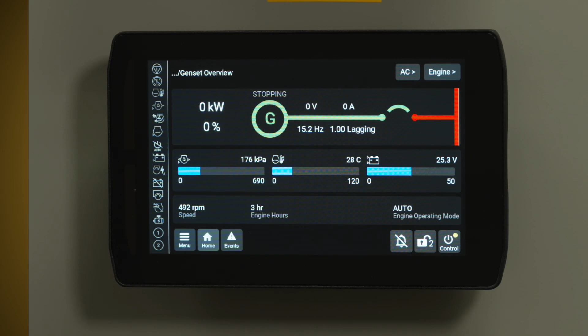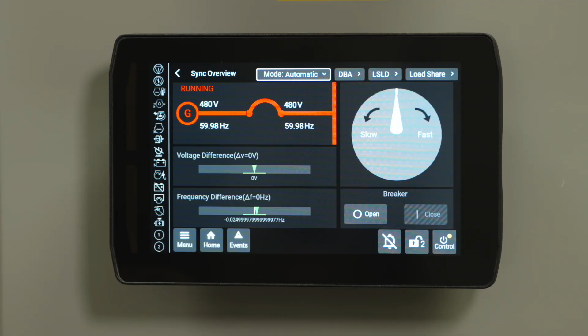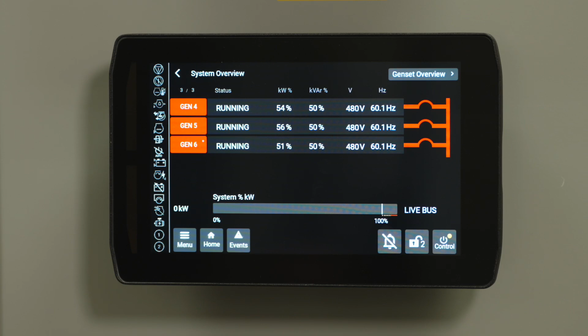As Vic has mentioned, we support enhanced PLC capability. This allows us to leverage Caterpillar logic and patented algorithms into features such as paralleling and load sharing. Just like our previous genset controller, we're able to see all gensets on the bus from any single display. Our gensets communicate over Ethernet using a Caterpillar proprietary protocol, APCDL, Advanced Paralleling Control Data Link.